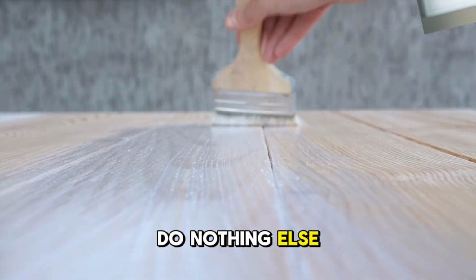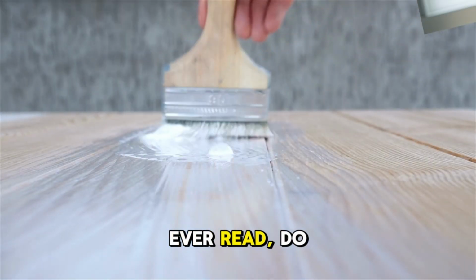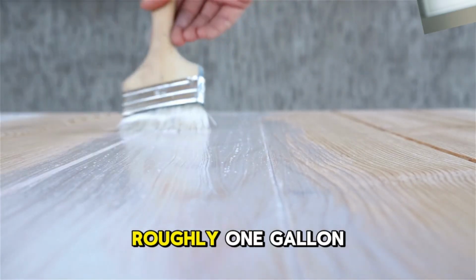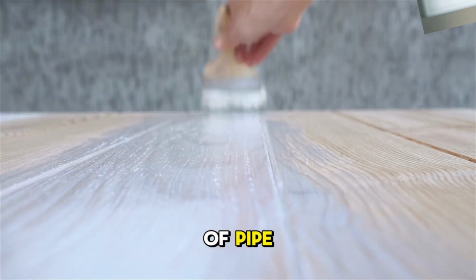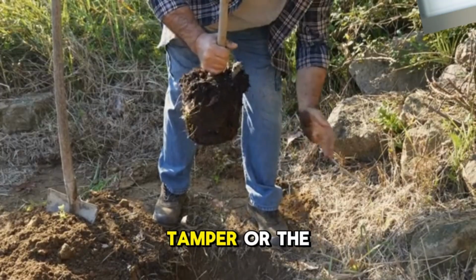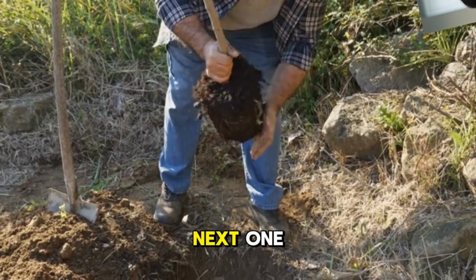If you do nothing else differently from every guide you have ever read, do this. Backfill in 6-inch layers. Wet each layer with roughly 1 gallon of water per 10 feet of pipe. Pack each layer down with a hand tamper or the flat back of a shovel before laying the next one.